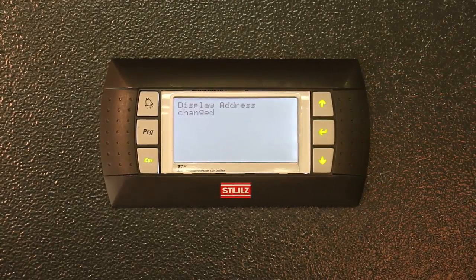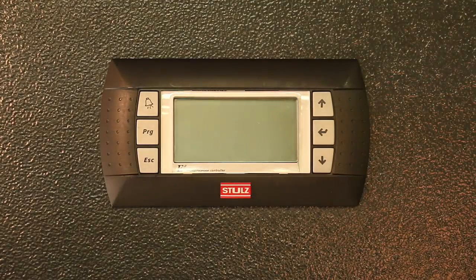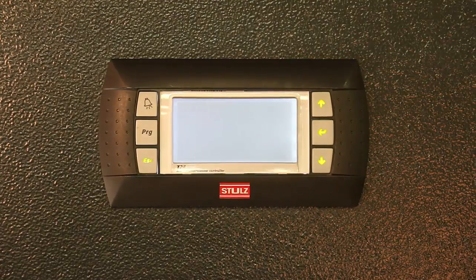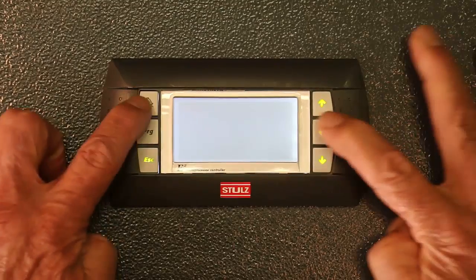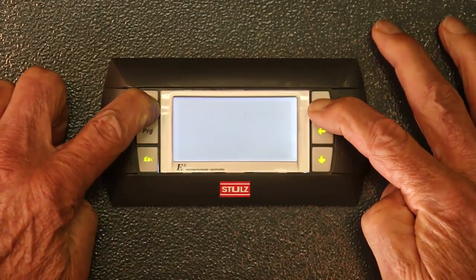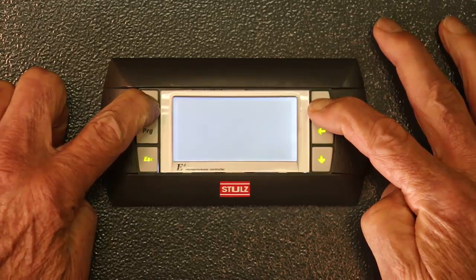Turn power off to the I.O. board and then turn it back on. During power up, you will need to press the alarm and up arrow buttons together until the words 'self test please wait' appear on the display.